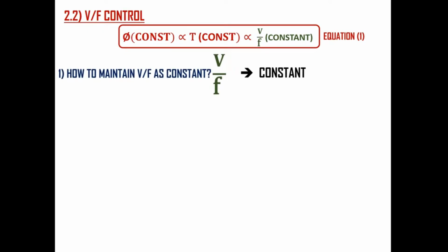If we increase the frequency, then we need to increase the voltage as well to keep the V by F ratio as a constant. As well as if we decrease the frequency, we have to decrease the voltage in order to maintain V by F ratio as a constant. Constant V by F ratio maintains the torque and flux as constant.